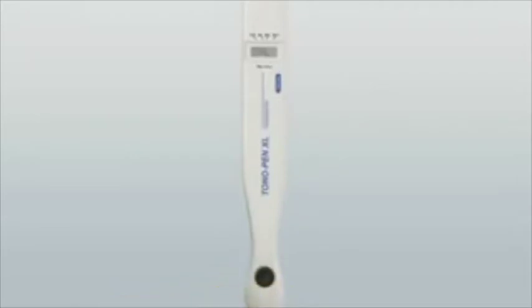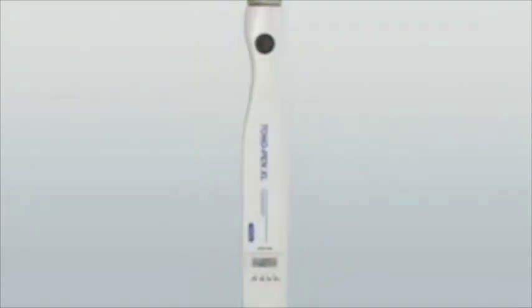Two beeps will sound, and CAL will appear on the LCD screen. Hold the probe in this position until a beep sounds. This may take up to 20 seconds. UP will then appear on the LCD screen. Immediately turn the probe 180 degrees so the tip is pointing straight up. In a few seconds, you will hear another beep. If the LCD reads GOOD, the calibration was successful and you are ready to use the device. If the LCD reads BAD, the calibration was unsuccessful and you will need to repeat the calibration process.